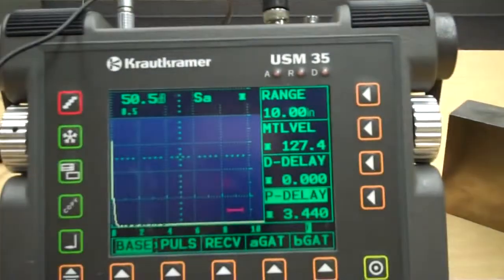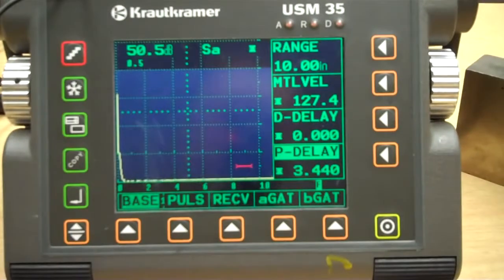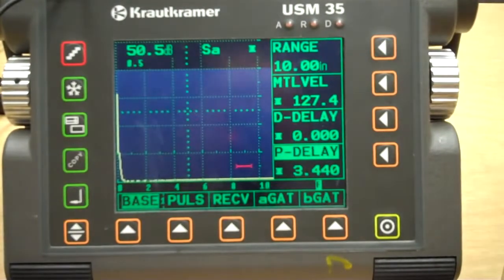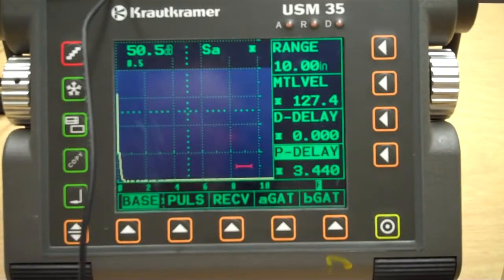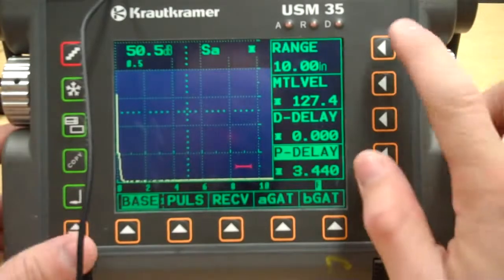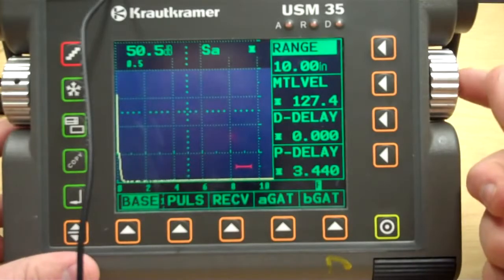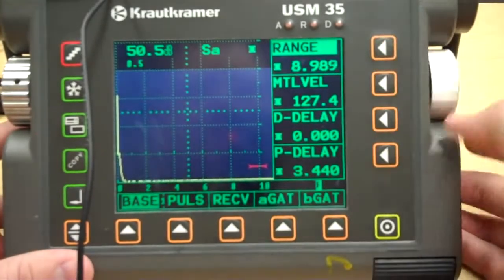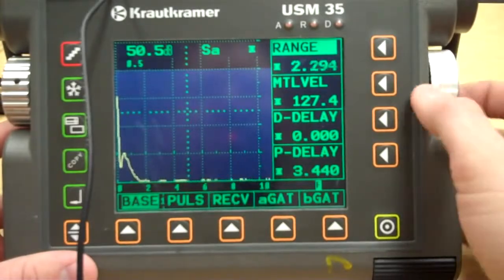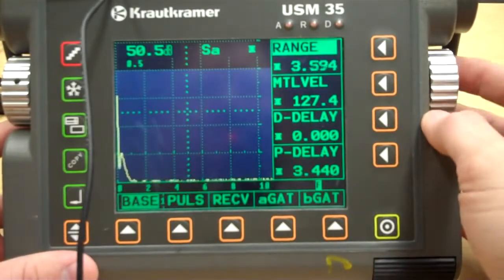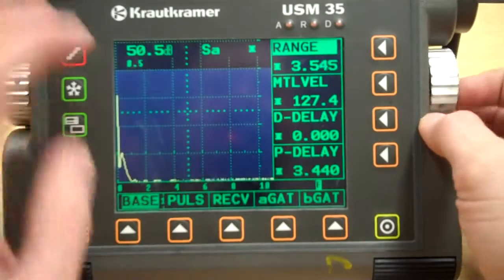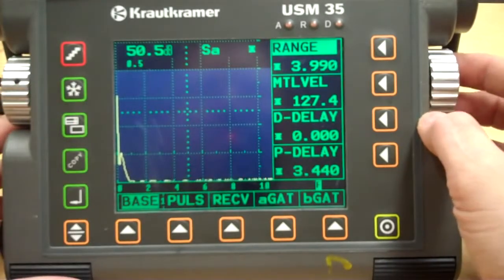So, we're going to come back to our scope here. We got just a regular piece of steel, which is what that is. Nav ships test block, or nav C test block, is just a regular old piece of steel. So we need to get to the compressional mode for steel, and then we need to make sure our screen range and everything is set up where we want it to be. So we're going to set up to a 3-inch range, actually a 4-inch range. That's what the lab says. So we'll go to a 4-inch range, and as you can see, this is a different scope than we used for the first couple of labs, but that's okay. They all do the same thing.